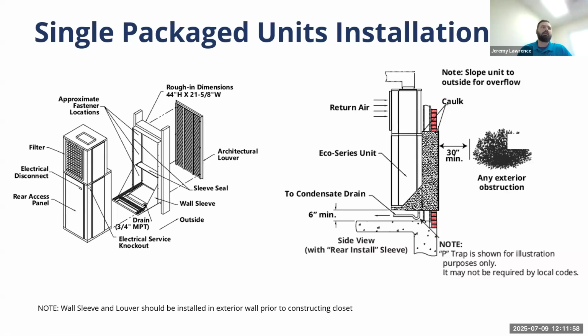So in cooling, any condensate that's created off the evaporator is drained down to the bottom of the unit and then into the sleeve, where you can see here it's trapped, and then would be piped to the closest sanitary drain. As well, the way that this sleeve is designed, if this trap or drain was to be plugged, the sleeve is designed to overflow water outside instead of into the building. So a double protection. And there are also overflow protection switches that can be added to the unit to actually shut the unit down if water gets to be an issue. But they are designed to drain into the sleeve and then out exterior to the building instead of causing any damage inside.